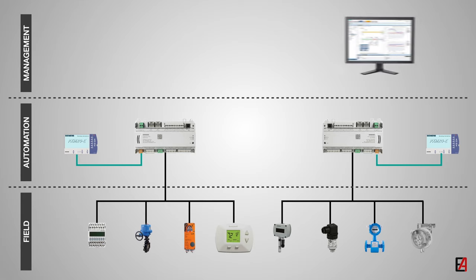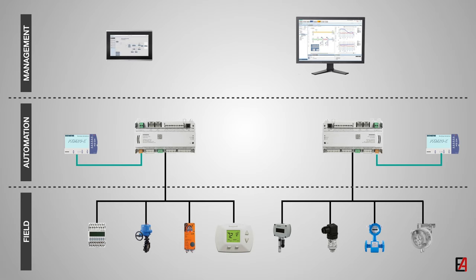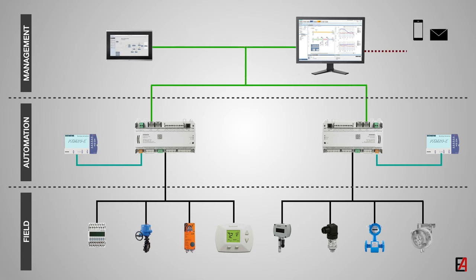Next is the management level. The management level provides an interactive user interface to the building operator. It displays all the information taken from the field level by the controllers in a graphical user interface format. The management level can either be a PC or an HMI — human machine interface. The management level can also send data via text or email message in case of any critical alarms. The field level sensors and devices are connected to the automation level via hardware connections, typically with single pair cables. The operator terminals can be connected either via a bus cable or a standard Ethernet cable. The automation level is connected to the management level via BACnet IP protocol with the use of building structured cable networks.